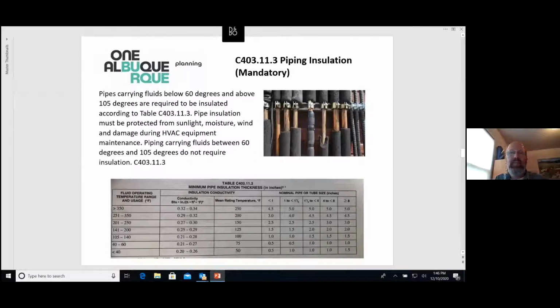Piping insulation. Now we're talking about mechanical piping insulation, not domestic water type stuff. Heating and chilling and cooling piping that's transferring fluids to the system to heat or cool. So if it's below 60 degrees or above 105, it's required to be insulated. And the chart on the bottom tells you, depending on the temperature, what the thickness of your insulation should be. So it's sizable, depending on how hot it is. The hotter it is, the more you want to retain it, so the thicker the insulation.